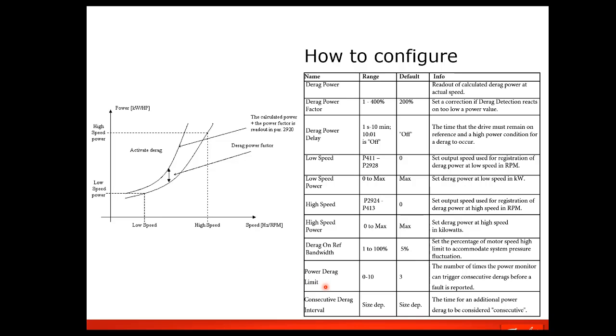And the number of times the power monitoring can trigger consecutively. So this is actually, if we're having a clog and it keeps on clogging, then we can trigger a fault if the drive cannot clear itself. And it'll give you a custom alarm code and wording on the screen saying the pump is clogged, it can't derag or declog it. And the number of times it can be consecutively deragging. So there's the timing and then the number.